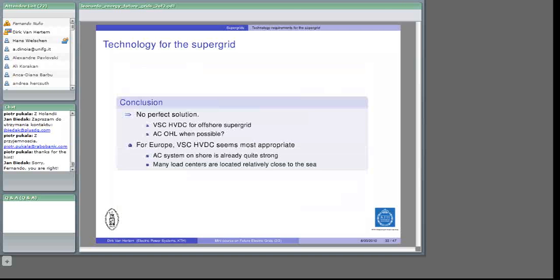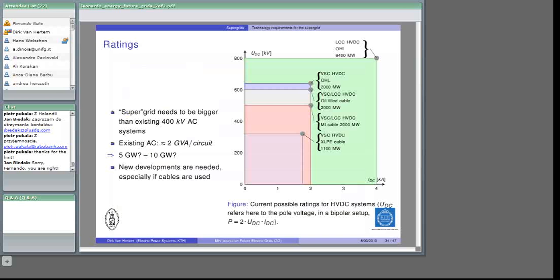First of all, it's not super if it's not bigger than what we have now, so it needs to be bigger than what we have now with 400 kV AC, and the existing AC system would be roughly about 2 gigavolt ampere per circuit. That means that if we go for a bigger one, we should go to 5 gigawatt, 10 gigawatt maybe, and for that new developments are needed. At this moment we are not near that amount, especially not if we want to have cables. For cables we are limited to about 2 gigawatt at this moment.